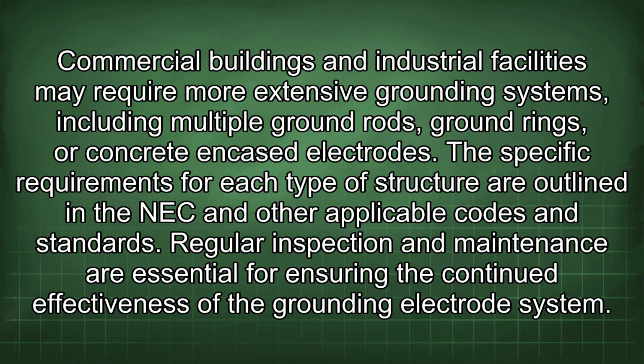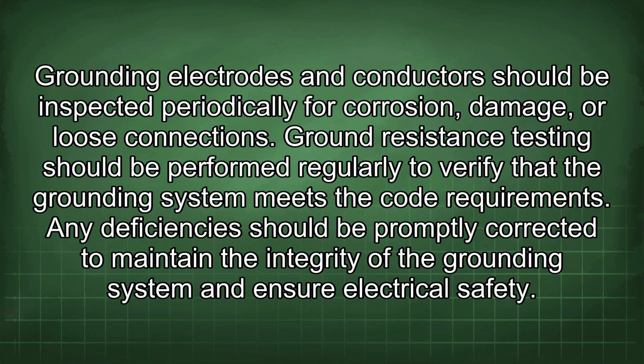Regular inspection and maintenance are essential for ensuring the continued effectiveness of the grounding electrode system. Grounding electrodes and conductors should be inspected periodically for corrosion, damage, or loose connections. Ground resistance testing should be performed regularly to verify that the grounding system meets the code requirements. Any deficiencies should be promptly corrected to maintain the integrity of the grounding system and ensure electrical safety.